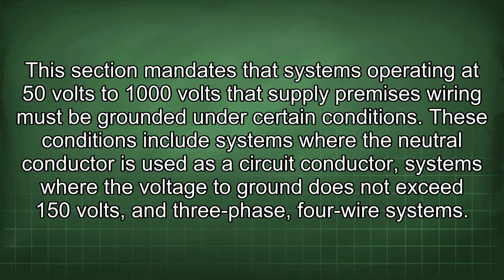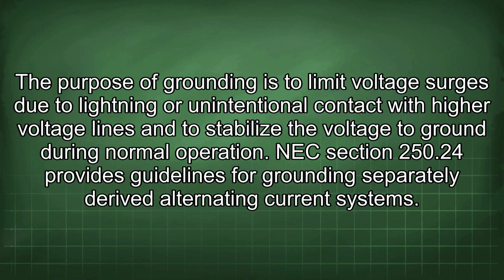This section mandates that systems operating at 50 volts to 1000 volts that supply premises wiring must be grounded under certain conditions. These conditions include systems where the neutral conductor is used as a circuit conductor, systems where the voltage to ground does not exceed 150 volts, and three-phase, four-wire systems. The purpose of grounding is to limit voltage surges due to lightning or unintentional contact with higher voltage lines and to stabilize the voltage to ground during normal operation.